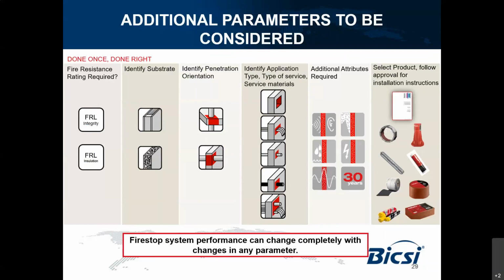We already explained this, linked to the previous block—we need to check what annular gap we need. Some systems also require us to check the percentage of cable fill. Some systems only support you filling, like the previous muffin example, up to about 60% cable in the opening. If the cable area is bigger than 60%, the opening is basically too small, and you need to find another solution. Additionally, there are certain additional attribute requirements—cable repenetration, acoustic requirements, water movement, aging, airflow control, air containment control, that sort of thing.